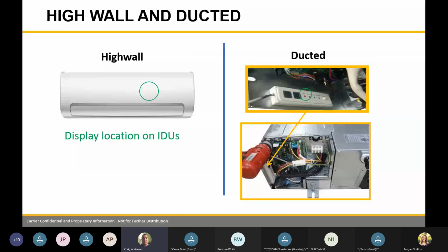So here's our high wall unit that we'd be looking at. So in your high wall unit, that'd be where the location of your error code is going to be on the high wall unit. It'll light up for you so you can see it, or the customer can see it and give you an idea before you get there of what that code is. If you're getting into ducted units, there's a little display box inside the ducted unit. If they left it inside the ducted unit, you're going to have to take the cover off the unit to get to see this display unit. If the guys have installed it, that bar is on a wire, so they could actually physically mount that on the outside of the unit if they wanted to. If they do, then now we don't have to take the unit apart to go in to see what that error code is. But on the ducted unit, it'll be on a bar just like that picture there, and that will give us our error code.